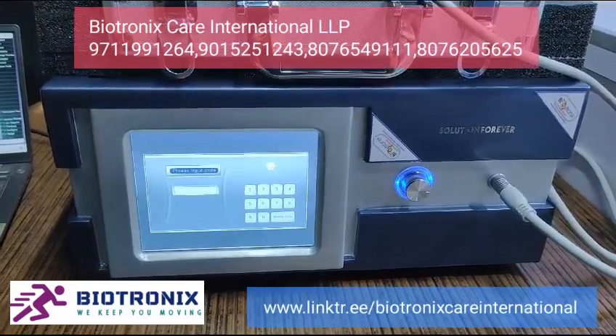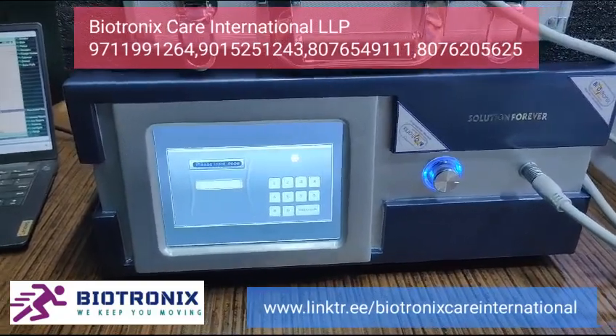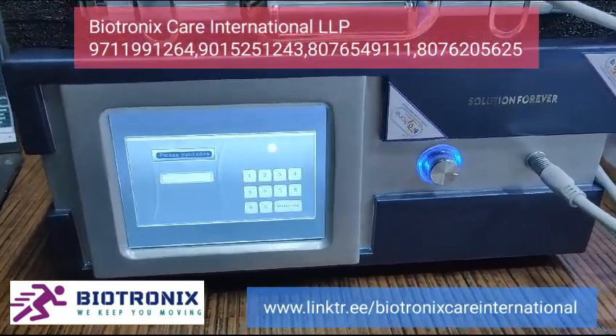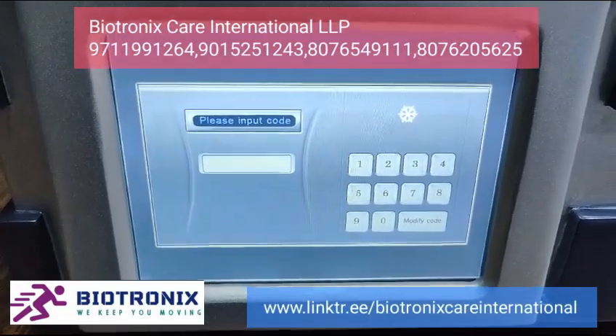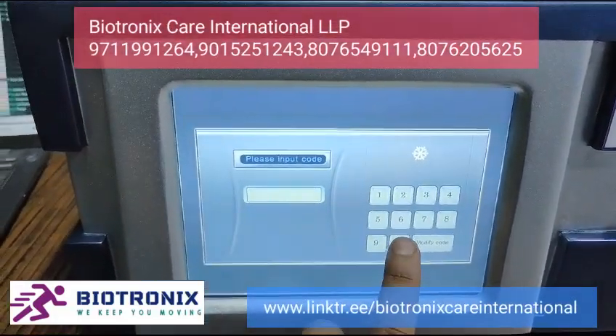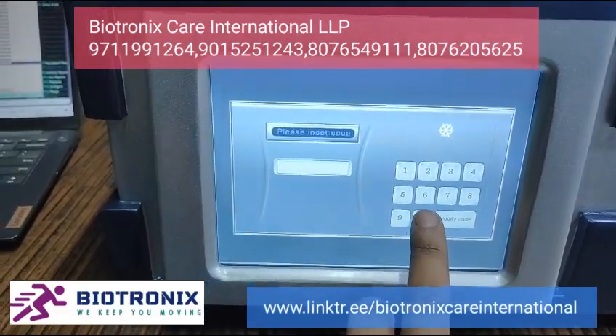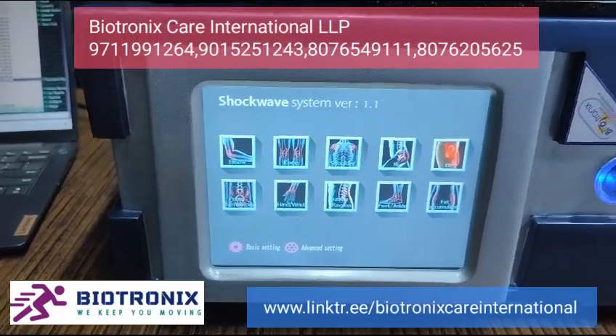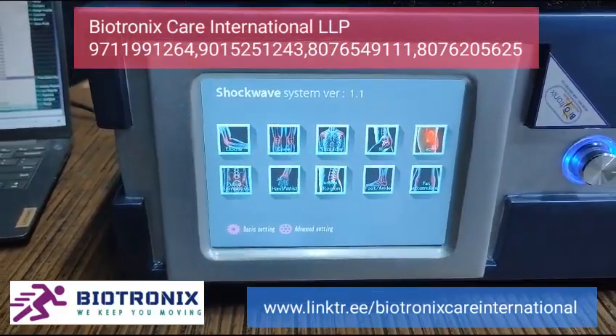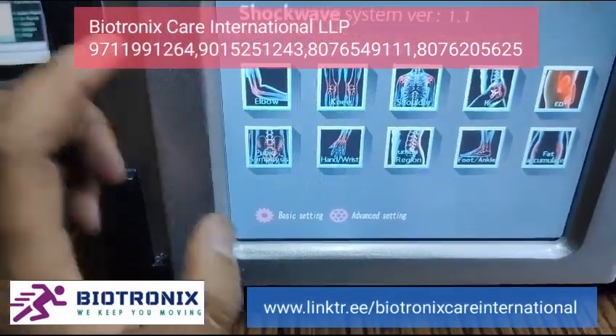Biotronix pneumatic shockwave — let me show you the parameters. Once you switch on the machine, you need to enter a password. The default password is 1-2-3-4-5-6. Enter it six times and press zero, and it will enter into the main screen.